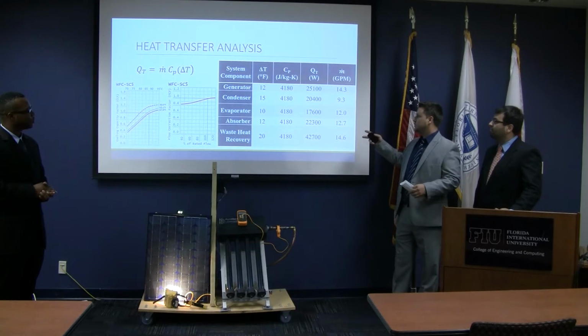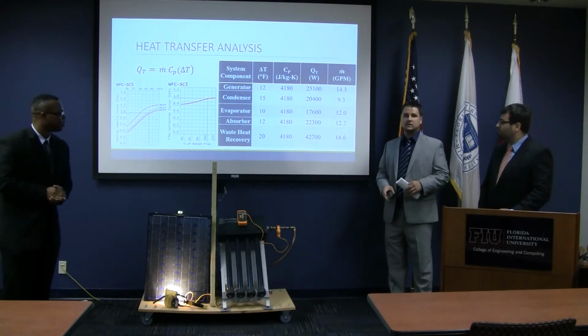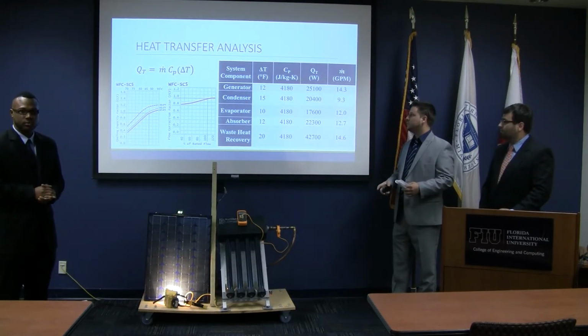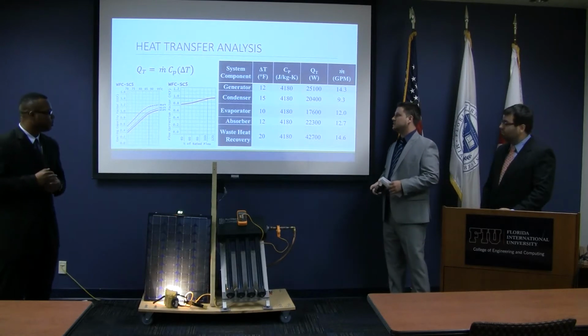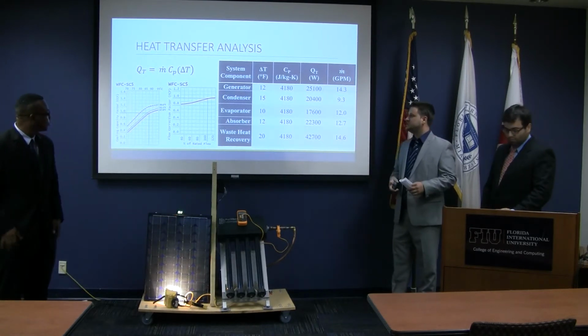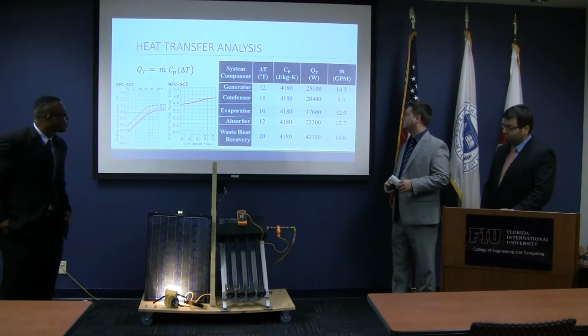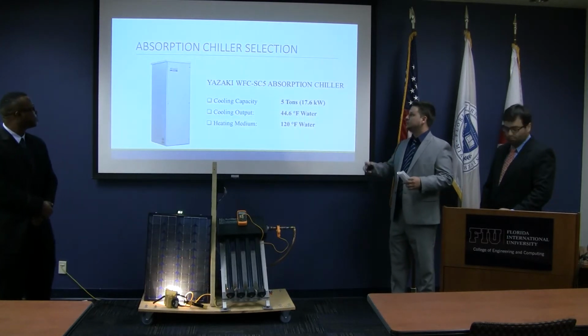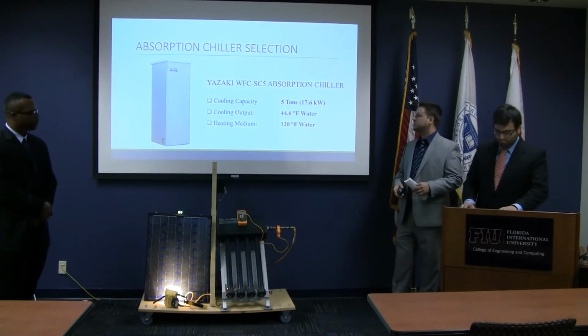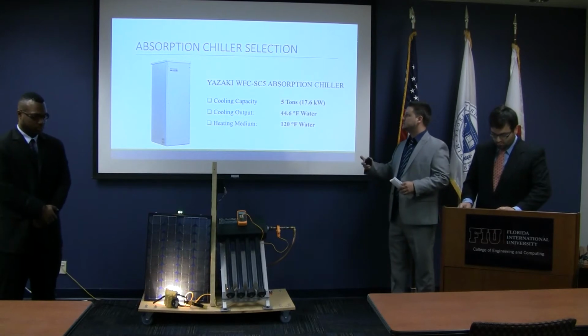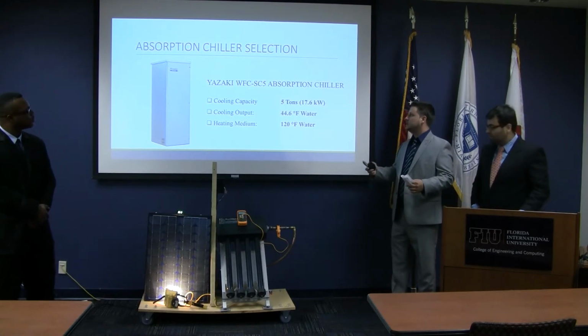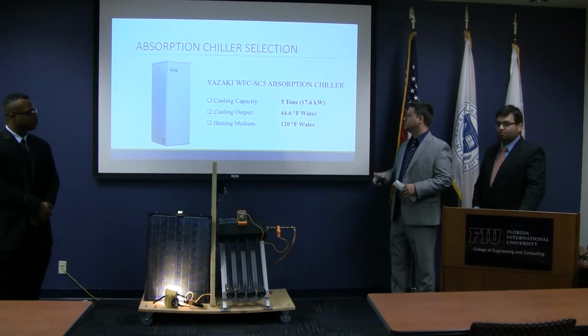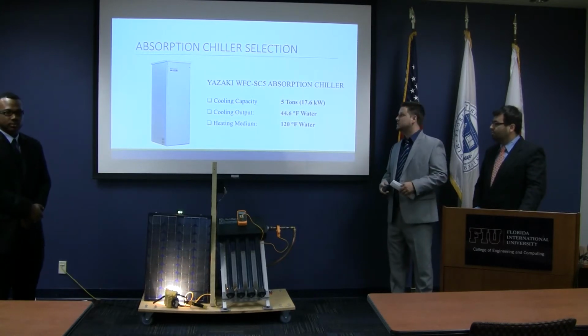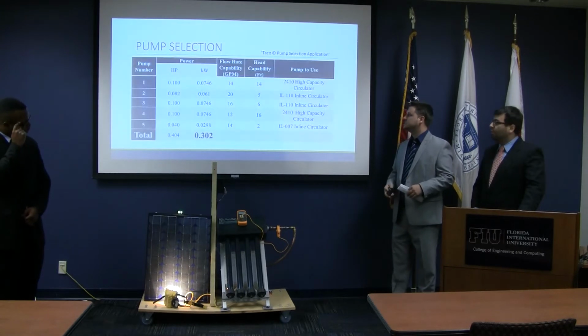These are the mass flow rates that we ended up finding with our desired temperature differences and heat input and output that we wanted. Taking into consideration, changing the temperature is going to change the capacity and also the flow through the system. So we chose the Yazaki absorption chiller, which is the water-fired chiller, 5 ton, one of the only 5 tons out there, but it's perfect for what we need, producing 44-degree water, which is used in evaporators or air handlers within a building to provide conditioned space.